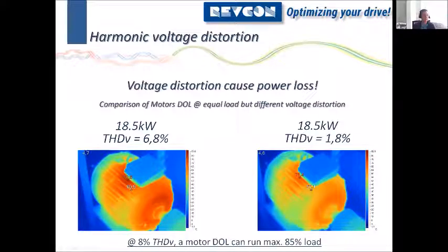So we tested this drive and let it run for, I think, 2 hours to get it saturated. And as you can see on the picture, there is roughly 5 to 10 degrees difference in these two motors just by changing the voltage distortion. And this doesn't give you a qualified picture of everything or every problem related to harmonics, but you can see on this that even though you have a standard motor, no drive, a motor direct online will suffer quite significantly from harmonic distortions.